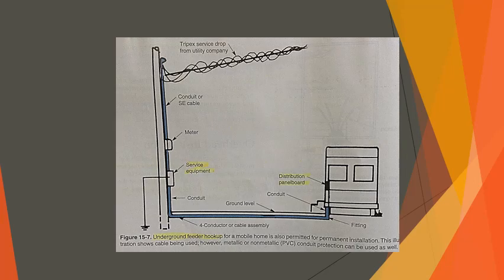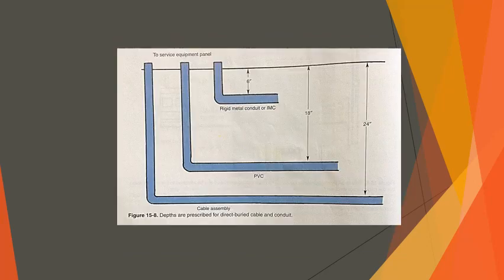An underground lateral service using cable or conduit. This is an alternative to an overhead permanent installation. It is the most common method used. See Figure 15-7. The underground lateral service must follow typical depth requirements based on the materials used. See Figure 15-8.